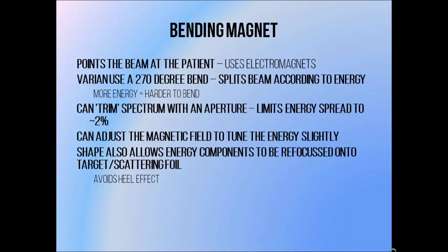The job of the bending magnet is to point the beam at the patient. In order to do this we like to use electromagnets, because when you pass electrons through a magnetic field they tend to follow a circular path. Electromagnets also allow us to adjust field strength, and different energies of electron beam require different strengths of magnetic field since more energetic electrons are tougher to bend.